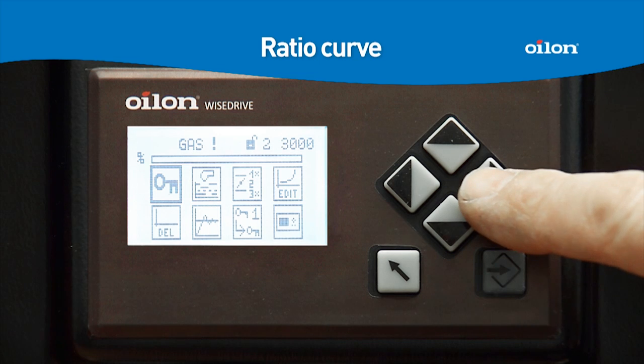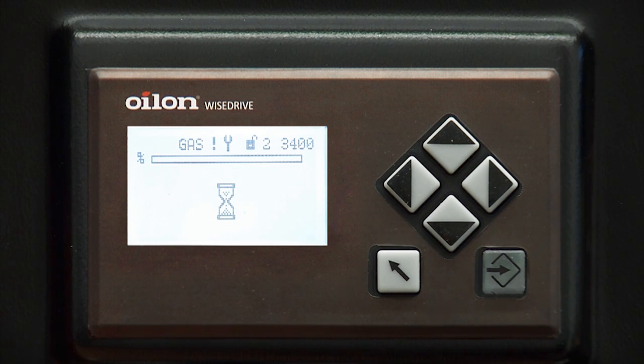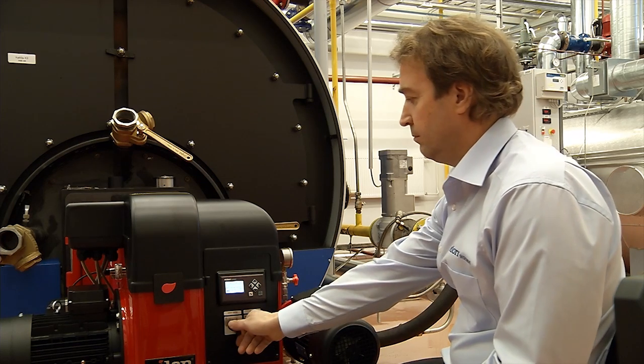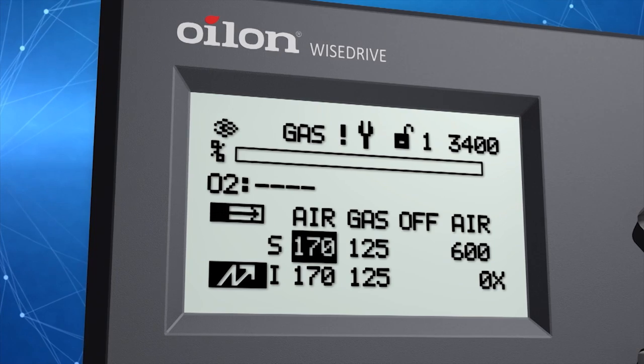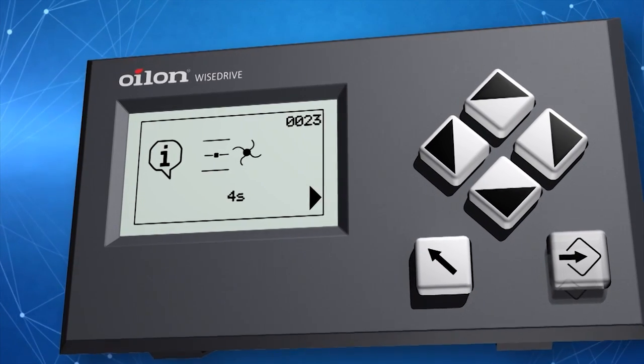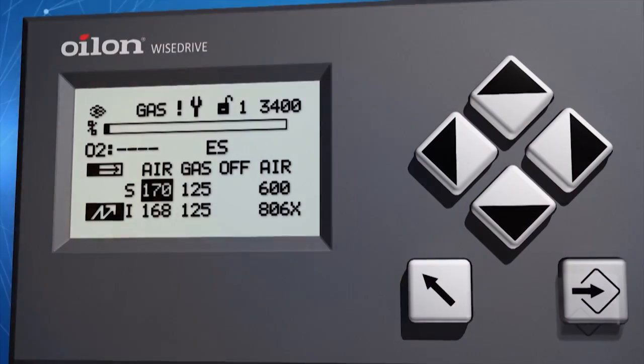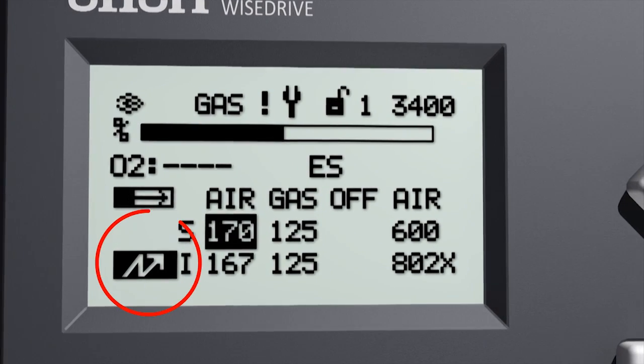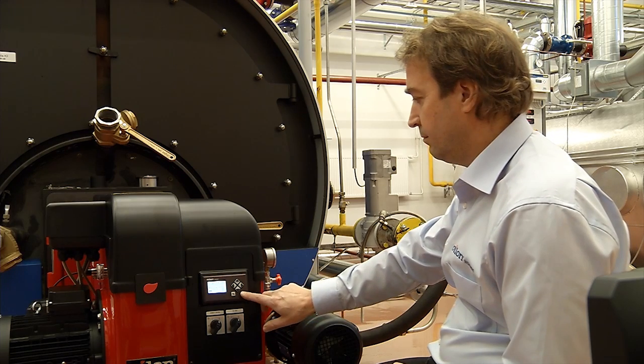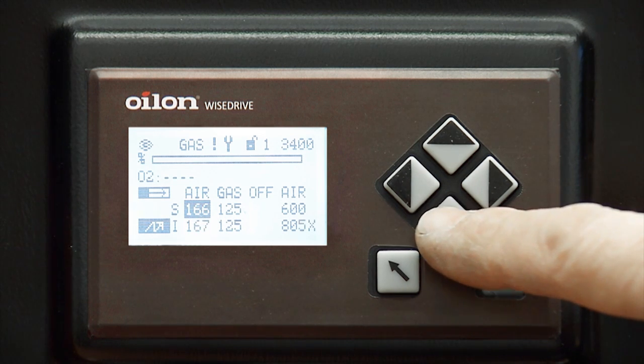Curves are set in the settings menu. Setting the curve starts with choosing the icon with a curve symbol and the word 'edit'. Pressing enter opens the menu and you can set the points. Start the burner. The first point is the ignition point and it is preset. You can see the symbol for the ignition point in the bottom corner. Changes are made by pressing enter. S is a set value and I is the value where the adjustment device is at the moment.